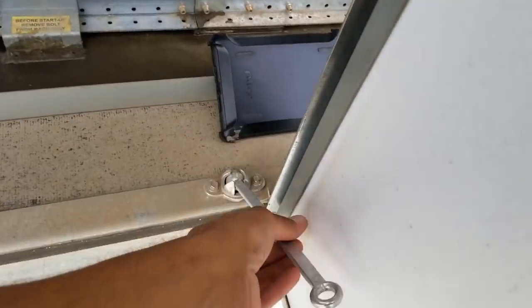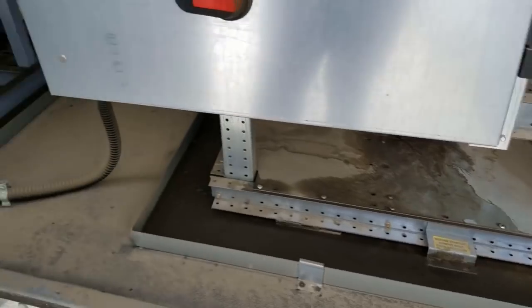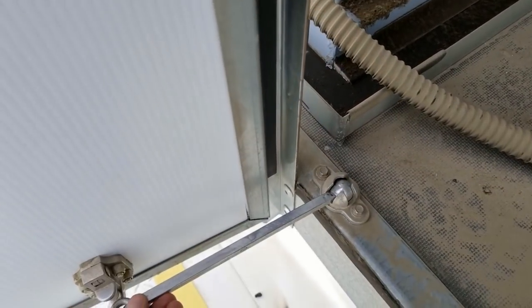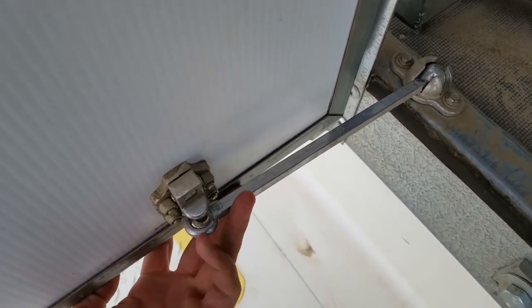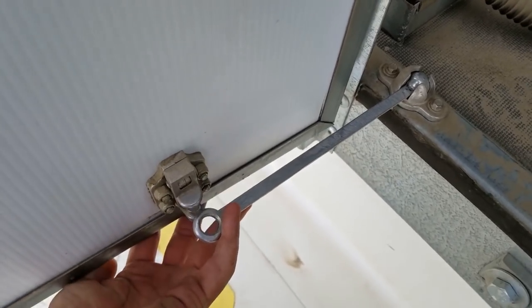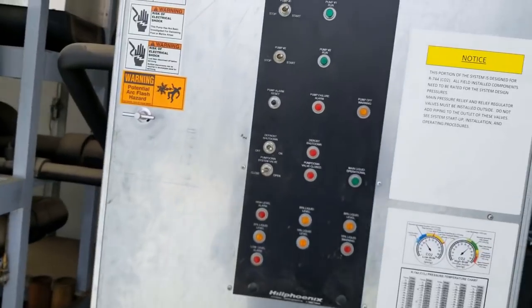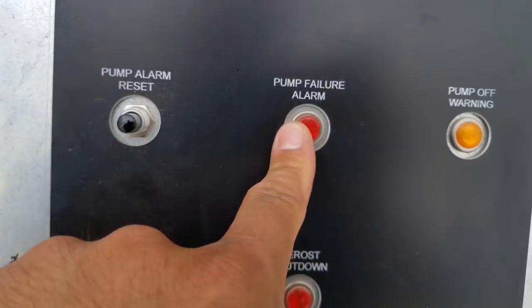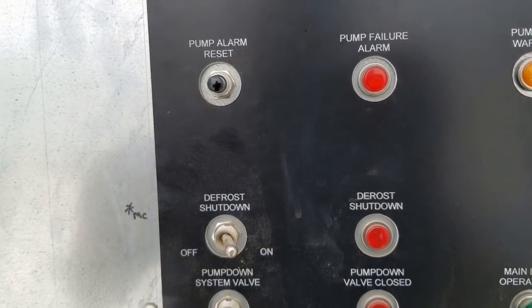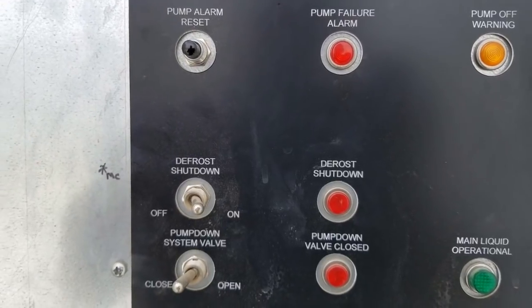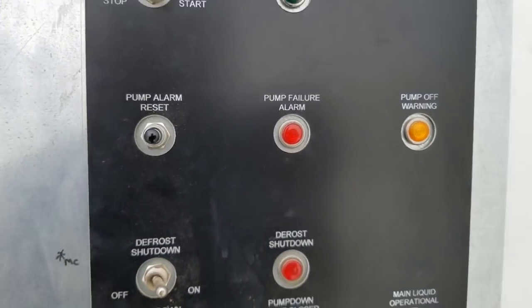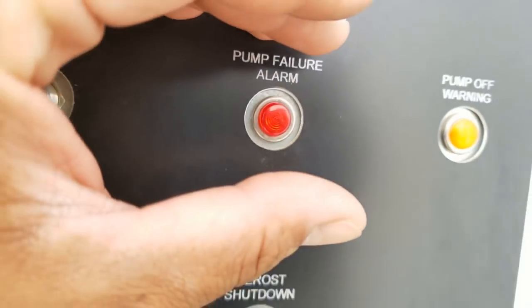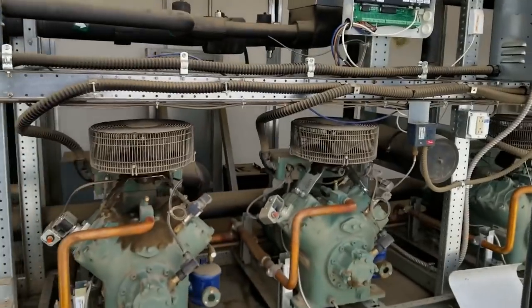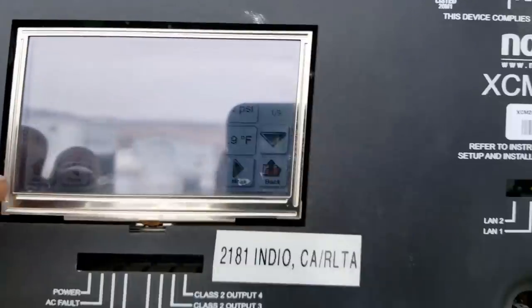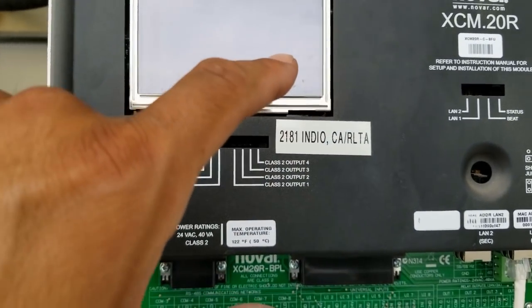I closed it. Let's see. It's up. I go open all the doors, right? Get in there. Oh well. It's not gonna go anywhere. The other door's open. So okay, you got a pump fail alarm because on your CO2 you have a pump safety at a certain pound, and we'll figure that out right now. I'm not too sure. I forgot what the low pressure is. I want to say 5 psi, but I'm not 100% sure on that. But we can find out in the controller. So let me get there and I'll show you guys.